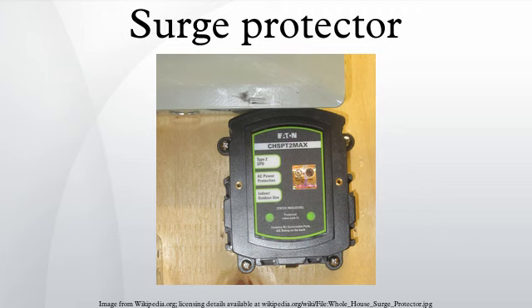NIST reports that sending surges down the drain of a grounding conductor only makes them reappear within a microsecond about 200 meters away on some other conductor. So having protection on a data transmission line is only required if surges are diverted to the ground line. In comparison to devices relying on 10-cent components that operate only briefly, SM devices tend to be bulkier and heavier than those simpler spike shunting components. The initial costs of SM filters are higher, typically $130 and up, but a long service life can be expected if they are used properly.